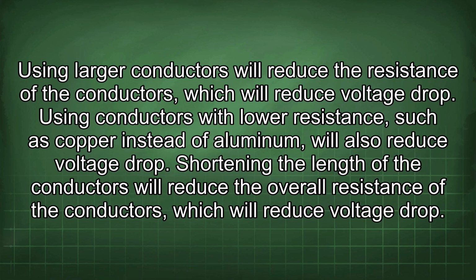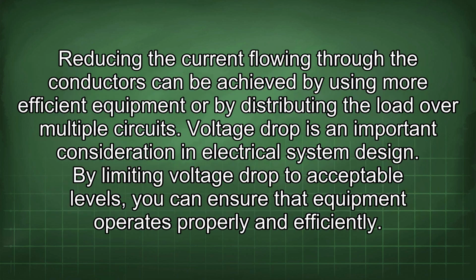Using larger conductors will reduce the resistance of the conductors, which will reduce voltage drop. Using conductors with lower resistance, such as copper instead of aluminum, will also reduce voltage drop. Shortening the length of the conductors will reduce the overall resistance of the conductors, which will reduce voltage drop. Reducing the current flowing through the conductors can be achieved by using more efficient equipment or by distributing the load over multiple circuits. Voltage drop is an important consideration in electrical system design. By limiting voltage drop to acceptable levels, you can ensure that equipment operates properly and efficiently.